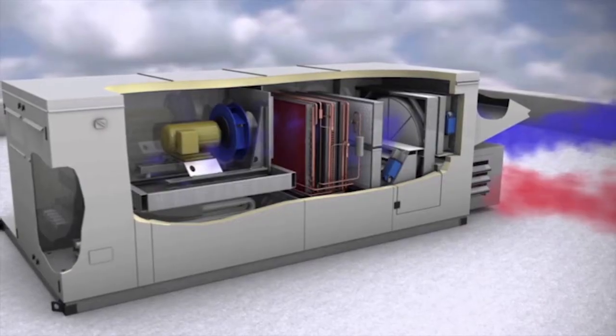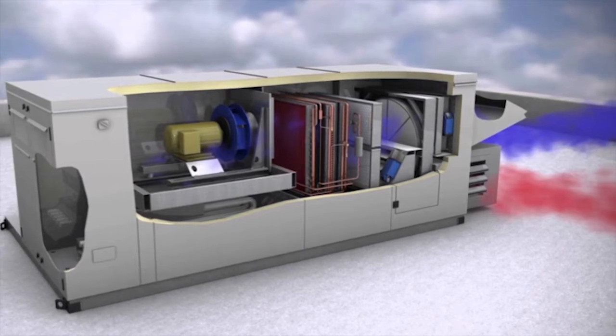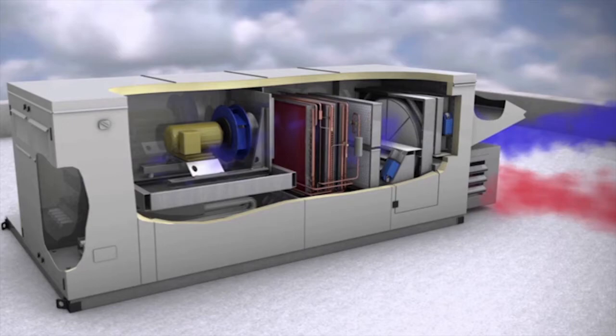For these two important considerations, a dedicated outdoor air system, or DOAS, was chosen. We chose a DOAS system because they are ideal ventilators that deliver 100% outside air to each zone of the building instead of stale, recirculated air that contains reduced oxygen and increased carbon dioxide levels. This type of system allowed us to exceed the air change requirements of ASHRAE 62.1.